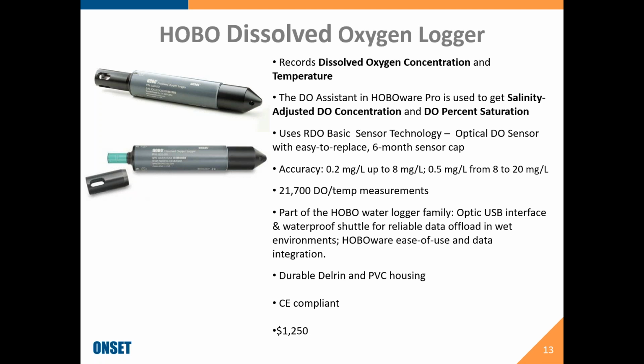It has an extremely rugged design. You'd use HOBOware Pro, the data assistant for DO, to get salinity adjusted DO concentration as well as percent saturation. Memory holds up to 21,700 combined DO and temperature measurements. This logger also collects temperature data and is supported by a base station or data shuttle.